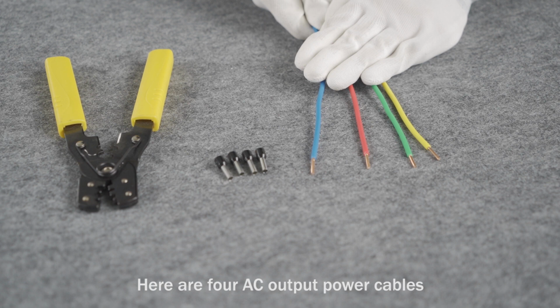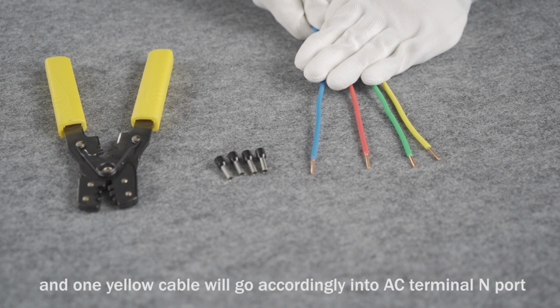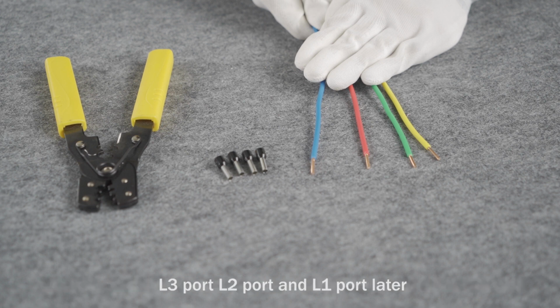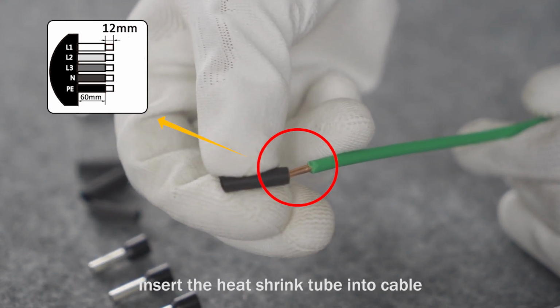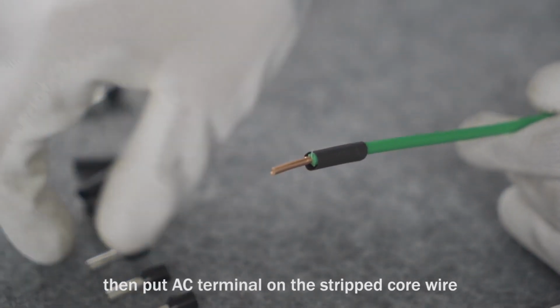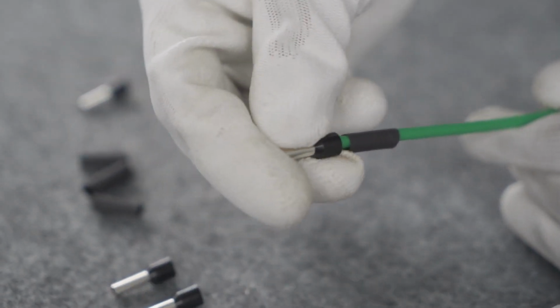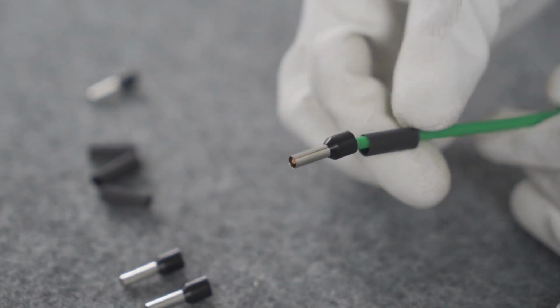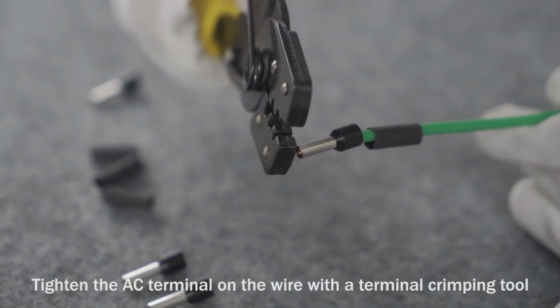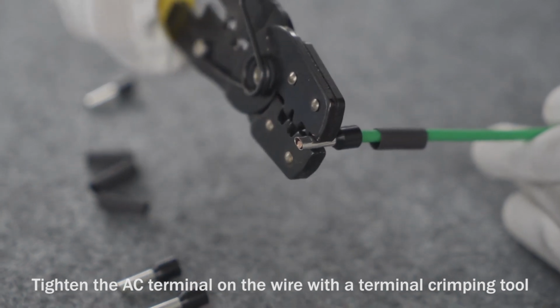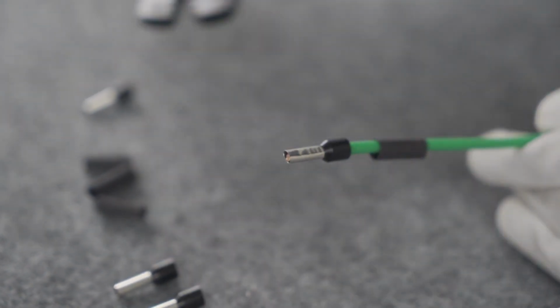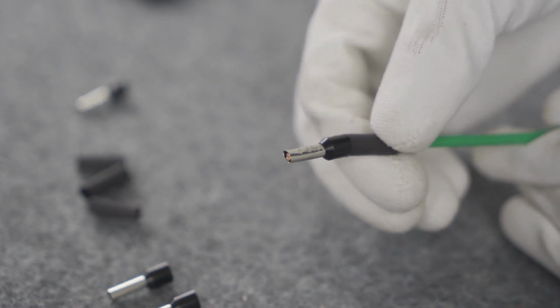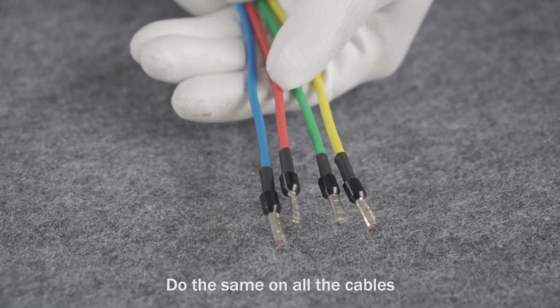Here are 4 AC output power cables. 1 blue cable, 1 red cable, 1 green cable, and 1 yellow cable will go accordingly into AC terminal N port, line 3 port, line 2 port, and line 1 port later. Insert the heat shrink tube onto the cable, then put the AC terminal on the stripped core wire. Tighten the AC terminal on the wire with a terminal crimping tool. Do the same on all the cables.